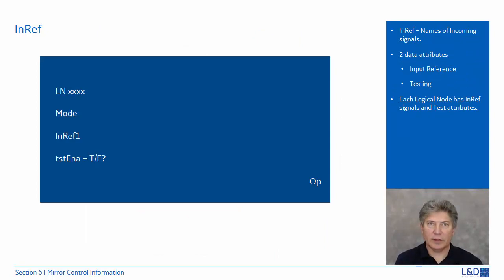Next, we'll look at InRef. To provide test inputs, Edition 2 supports a naming of incoming signals in a special reference data object at each logical node known as InRef. These data objects are broken down into two data attributes. One is a reference to the object normally used as an input, and the other is a reference to the data object used for testing. Testing allows us to virtually disconnect the terminal blocks.